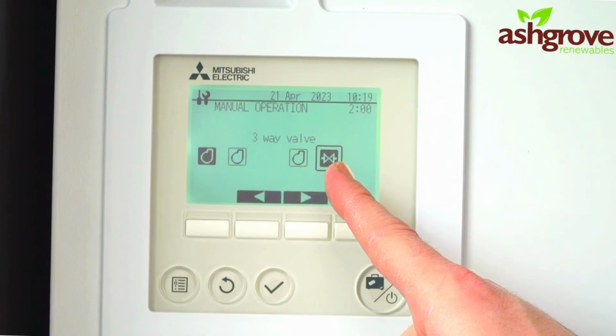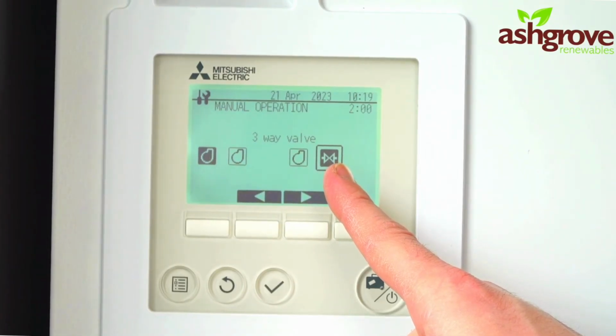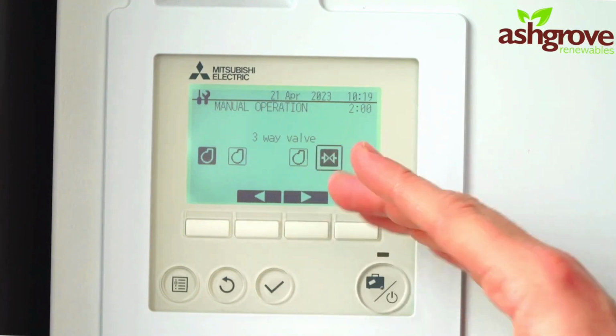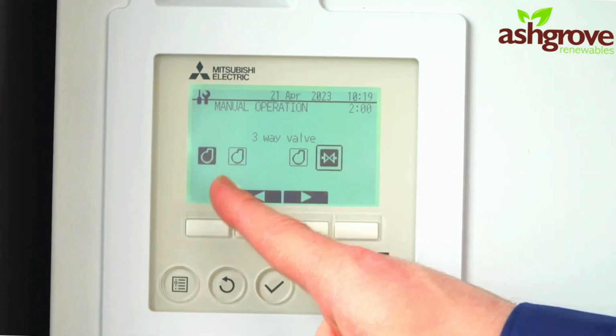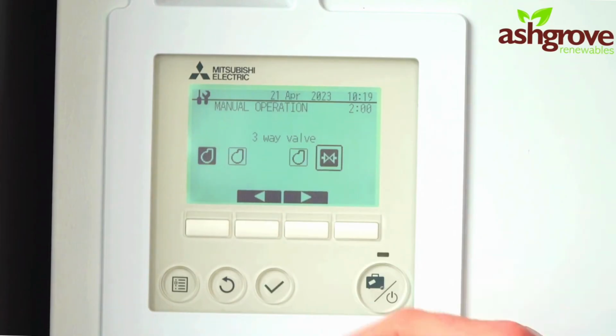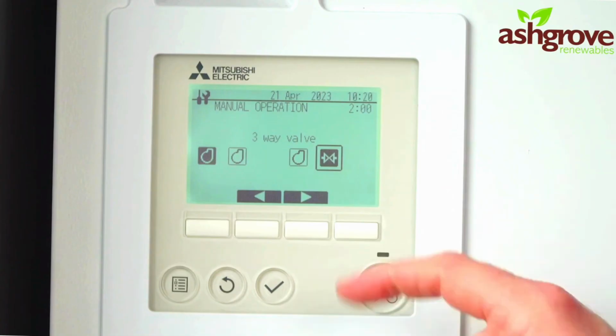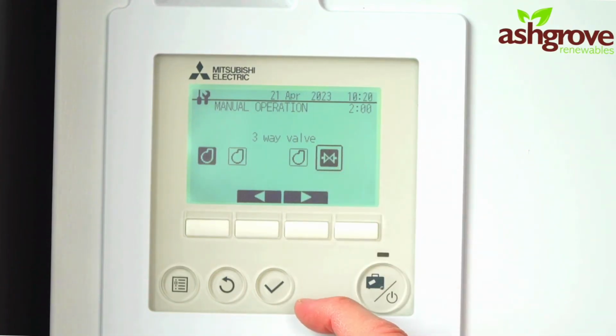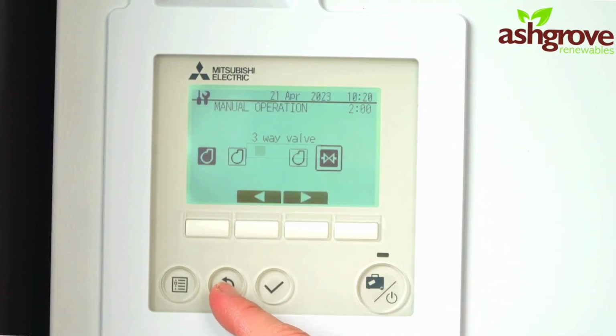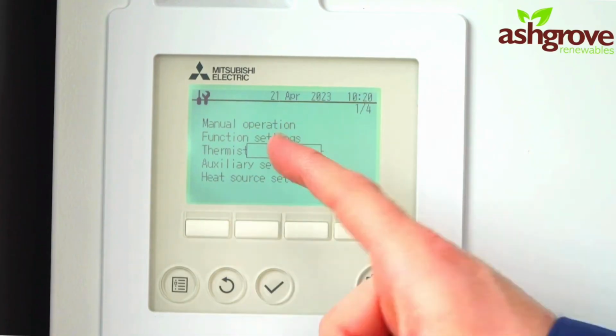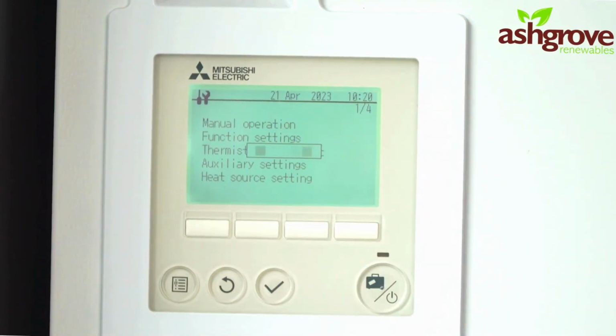So for a new installation where you wanted to flush the lines on both heating and hot water, and if you have power to your controller, you can simply go into manual operation, activate your primary pump, activate your 3-port valve to flush the entire system, to get the air out of the system. To come back out, simply click the anti-clockwise button once and you're back in the service menu. All pumps will turn off.